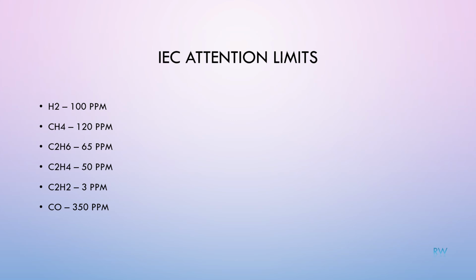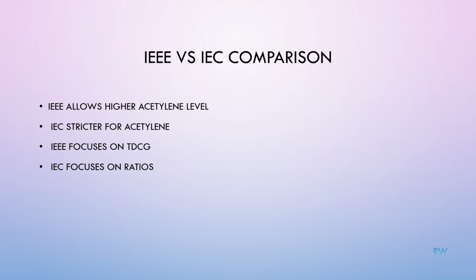Under IEC guidelines, hydrogen 100 ppm, methane 120 ppm, ethane 65 ppm, ethylene 50 ppm, carbon monoxide 350 ppm. However, acetylene attention level is only 3 ppm. This makes IEC more sensitive to early arcing detection compared to IEEE. IEEE allows higher acetylene levels before classifying severe condition. IEC treats acetylene more strictly. IEEE emphasizes total gas condition levels. IEC emphasizes ratio-based interpretation. Consistency in applying one standard is important for reliable trending.